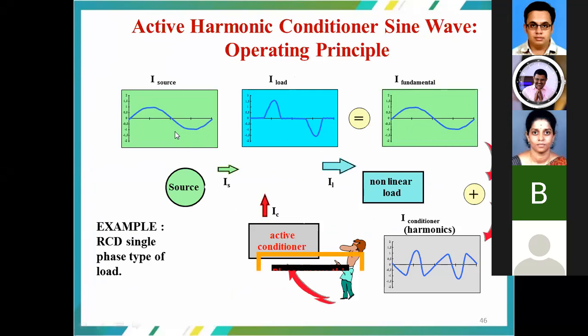So we are going to have the source, which is always going to apply the pure sinusoidal waveform. And because of the load, which is nonlinear, that is the non-sinusoidal component, which is going to be the RCD type. Due to this, we are going to have the effect in the fundamental component. So this fundamental component is going to get added with the nonlinear load, and you are going to have the harmonics as shown. That is the I conditioner. So this I conditioner is going to get injected into the system such that the net effect on the source is going to be nullified. So this is the pictorial, the simulation representation.